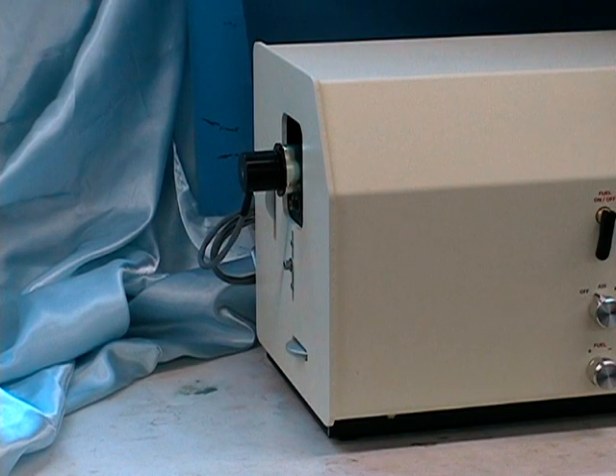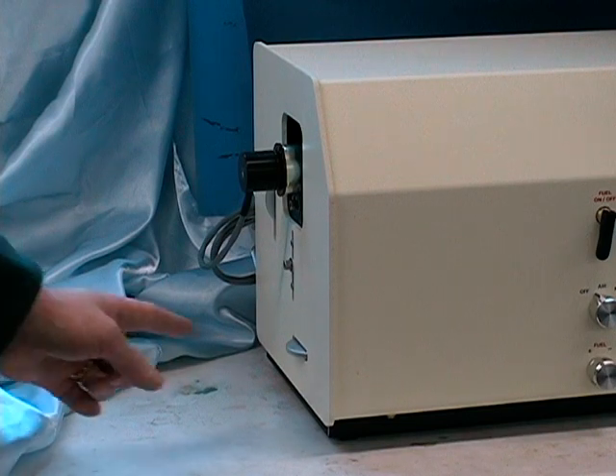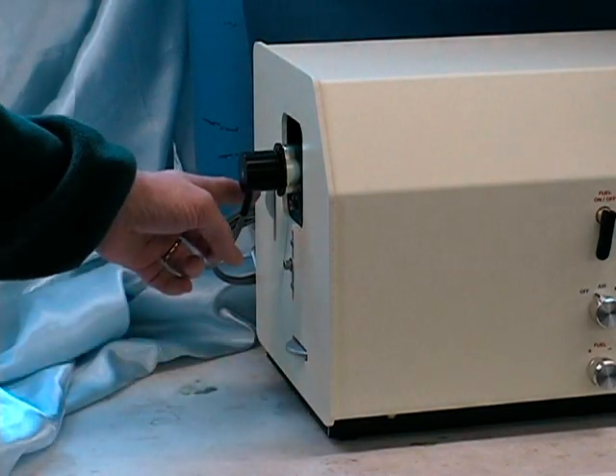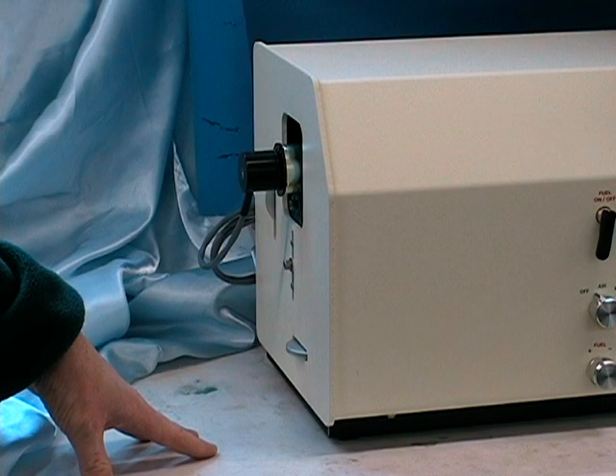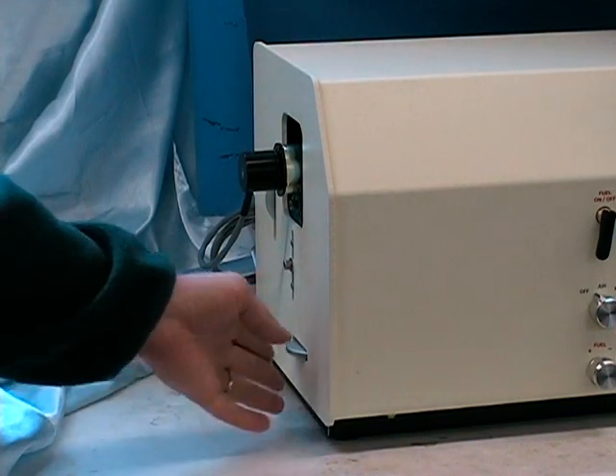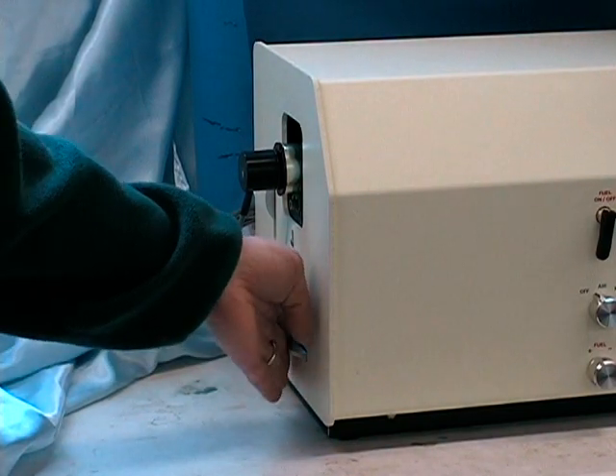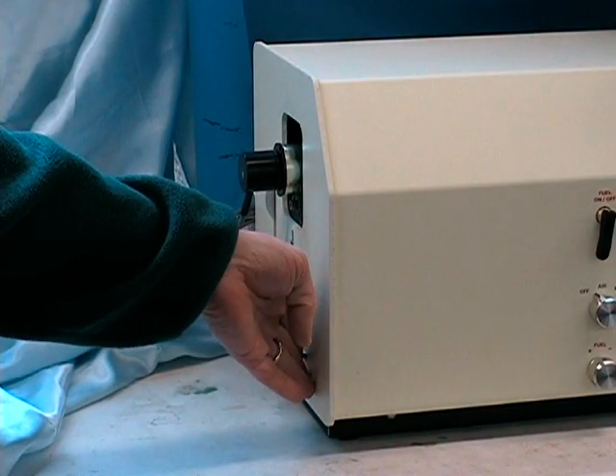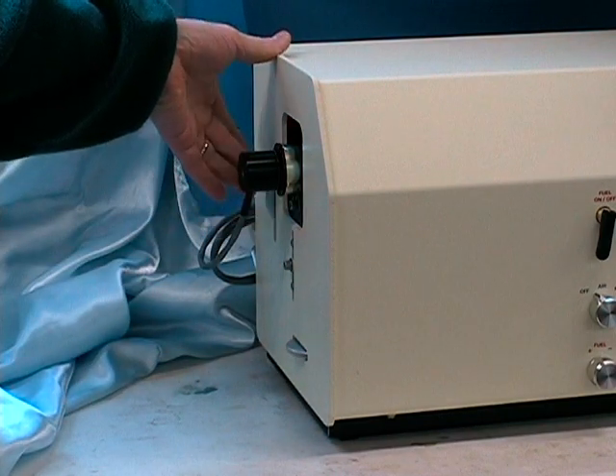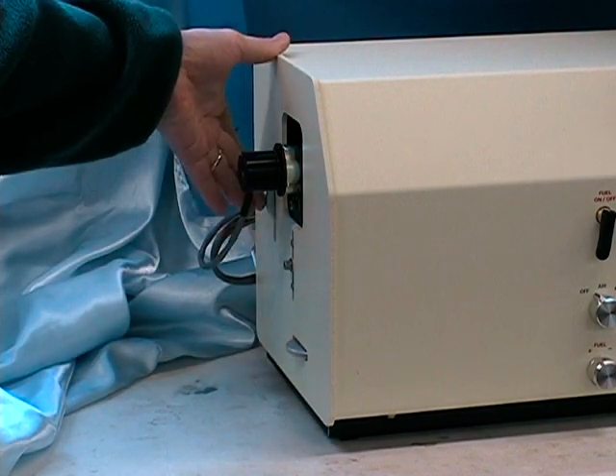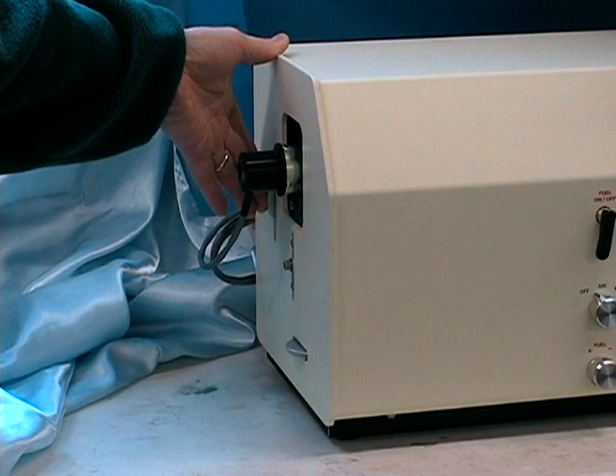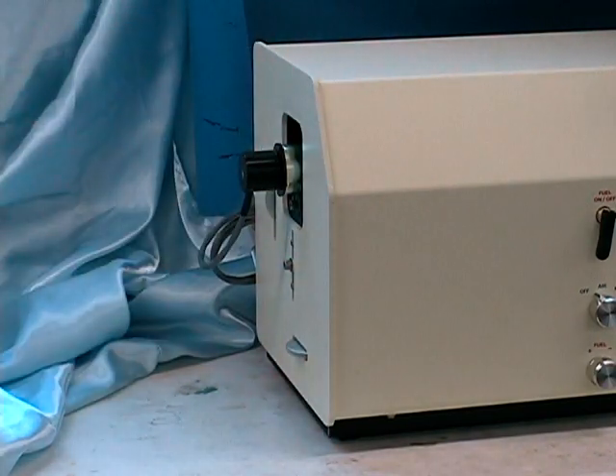The lamp holder assembly on the left side of the 205 AA system includes 2 silver knobs to adjust the horizontal and vertical positioning of the lamp so that the beam is centered into the optical system. Rotate those knobs 1 or 2 revolutions or more if necessary, while observing the bar graph or the sample energy reading to see if the energy can be increased even further. This will allow you to get the best detection limits and have the best stability possible.